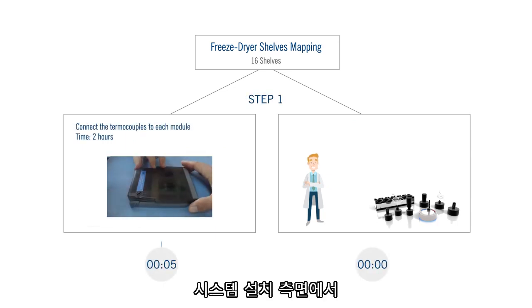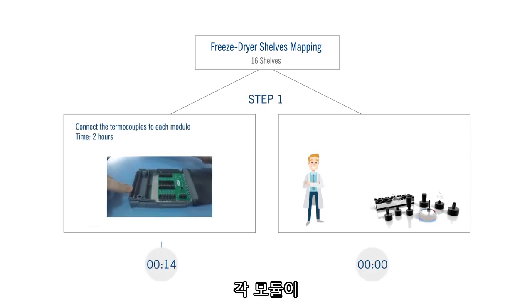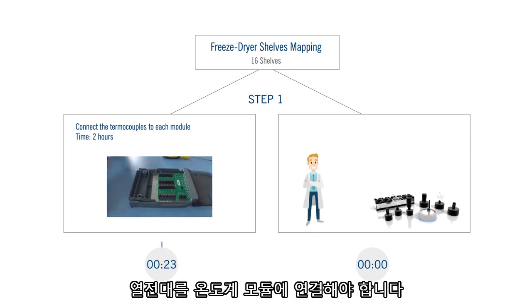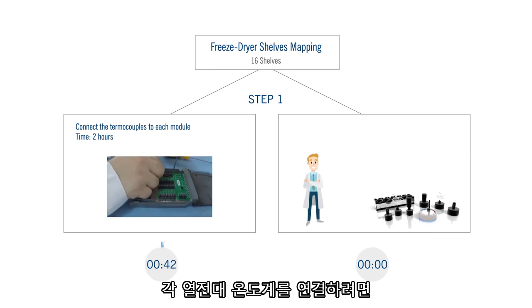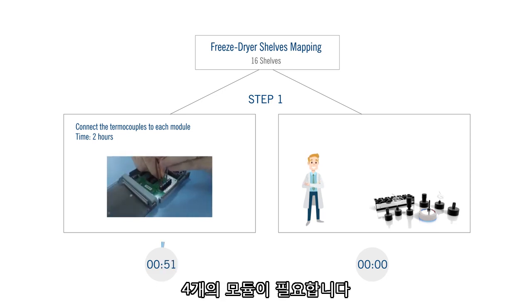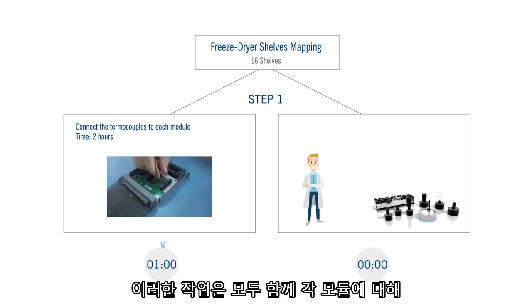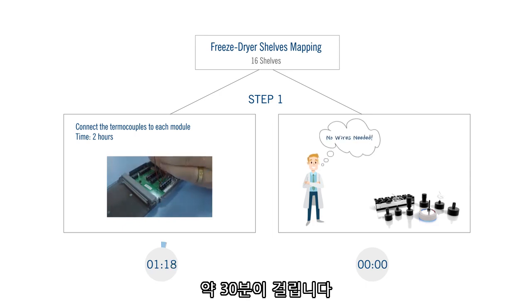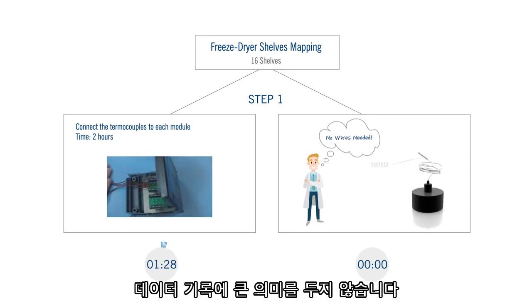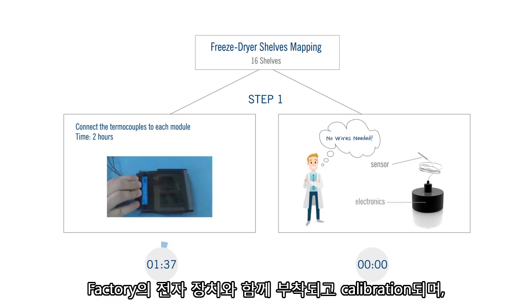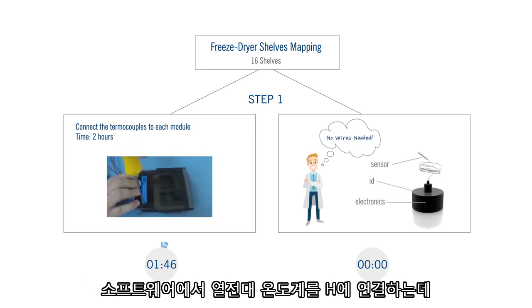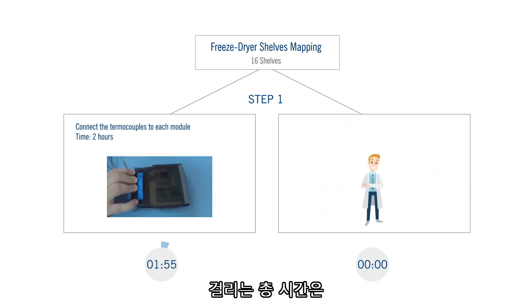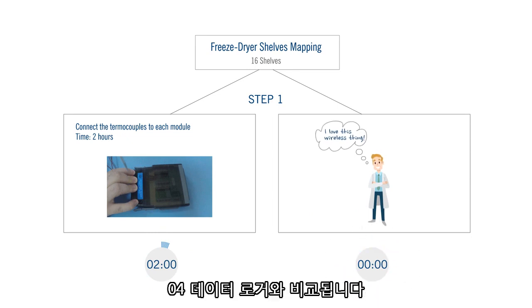In terms of installing the systems, the TC system requires the thermocouples to be connected to the modules. As each module may accommodate 20 thermocouples, 4 modules are needed to connect 80 thermocouples. Each thermocouple also needs to be labeled, and altogether these tasks take roughly 30 minutes for each module. This step is not needed for data loggers, as each data logger has the sensor attached and calibrated together with the electronics from factory, with the ID shown on the logger and in the software. Total time to connect the thermocouples, 2 hours versus 0 for data loggers.